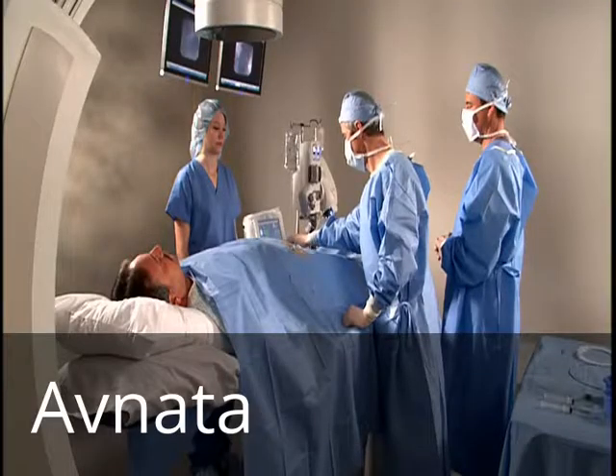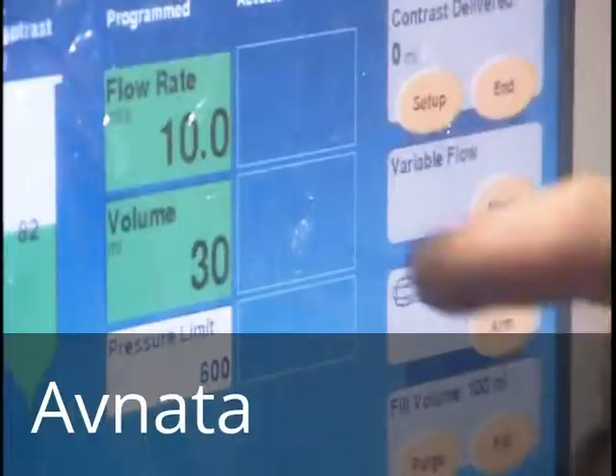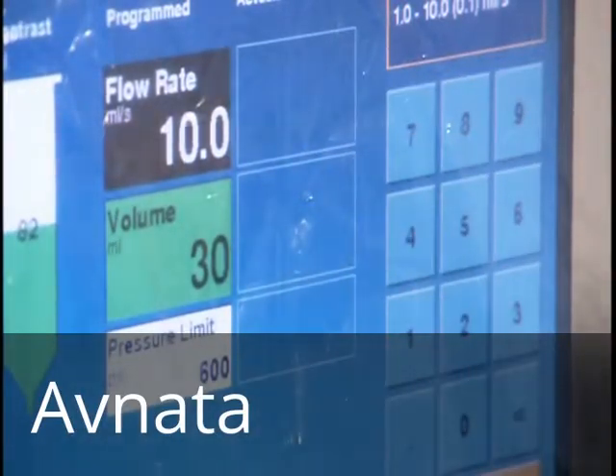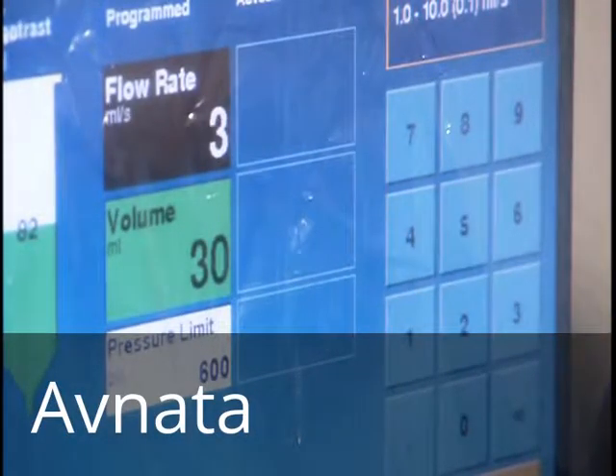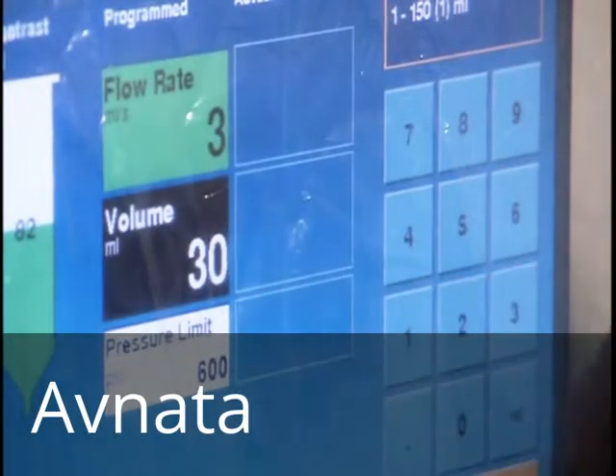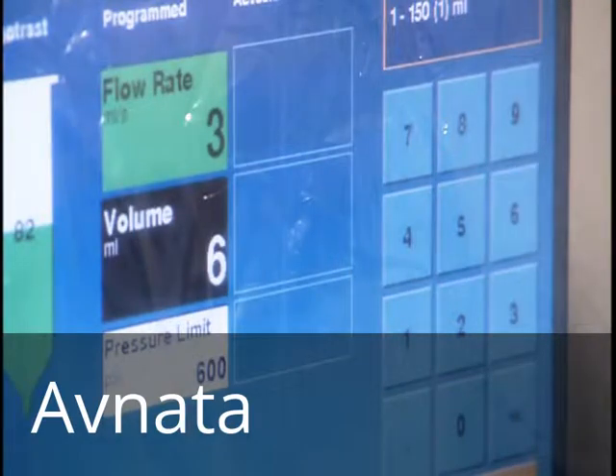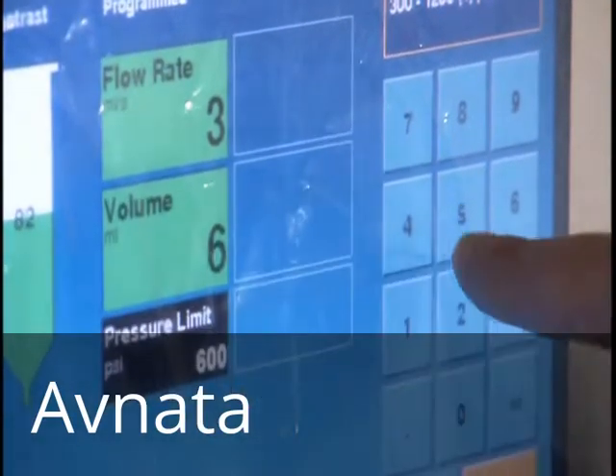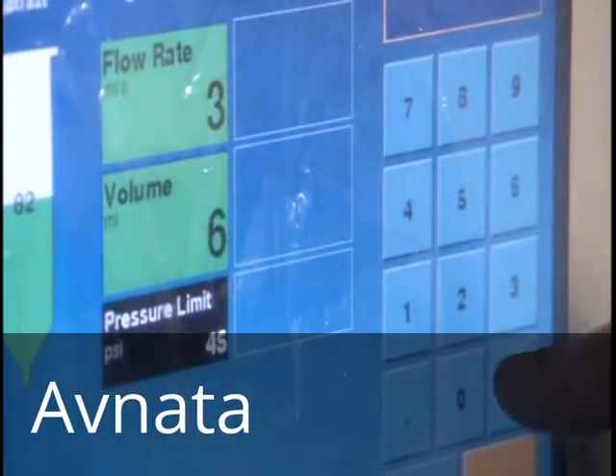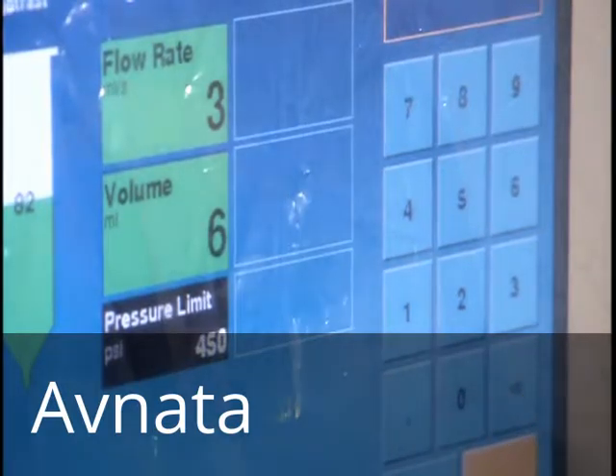To program a contrast flow rate in the variable mode, enter 1 to 10 milliliters per second in 0.1 milliliter increments on the touch screen. Next, program a volume from 1 to 150 milliliters. Then program a pressure limit from 300 to 1200 psi based on the catheter rating.